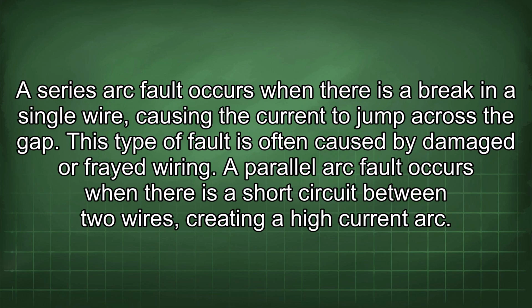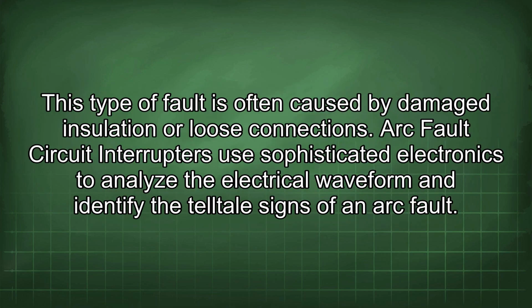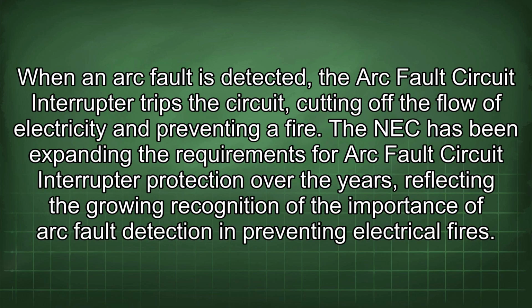A series arc fault occurs when there is a break in a single wire, causing the current to jump across the gap. This type of fault is often caused by damaged or frayed wiring. A parallel arc fault occurs when there is a short circuit between two wires, creating a high current arc. This type of fault is often caused by damaged insulation or loose connections. Arc fault circuit interrupters use sophisticated electronics to analyze the electrical waveform and identify the telltale signs of an arc fault. When an arc fault is detected, the arc fault circuit interrupter trips the circuit, cutting off the flow of electricity and preventing a fire.